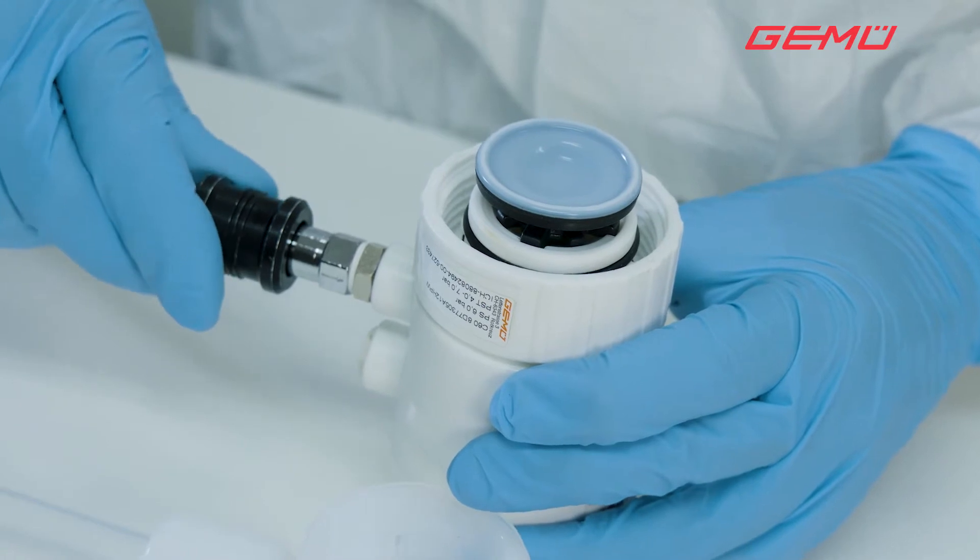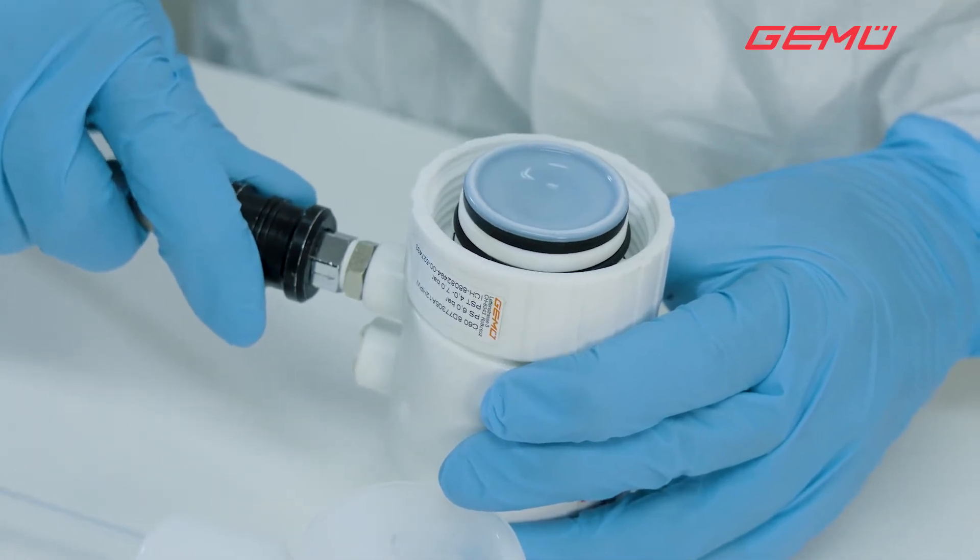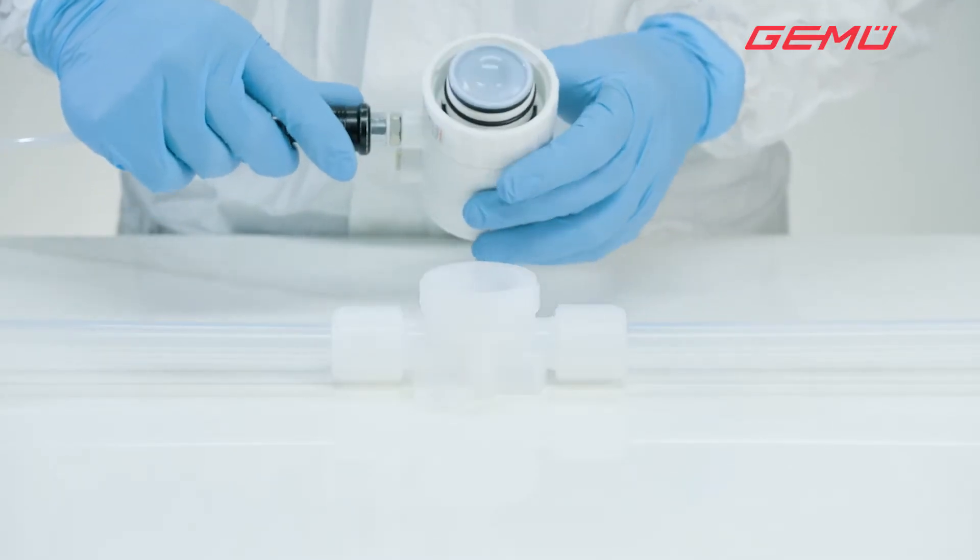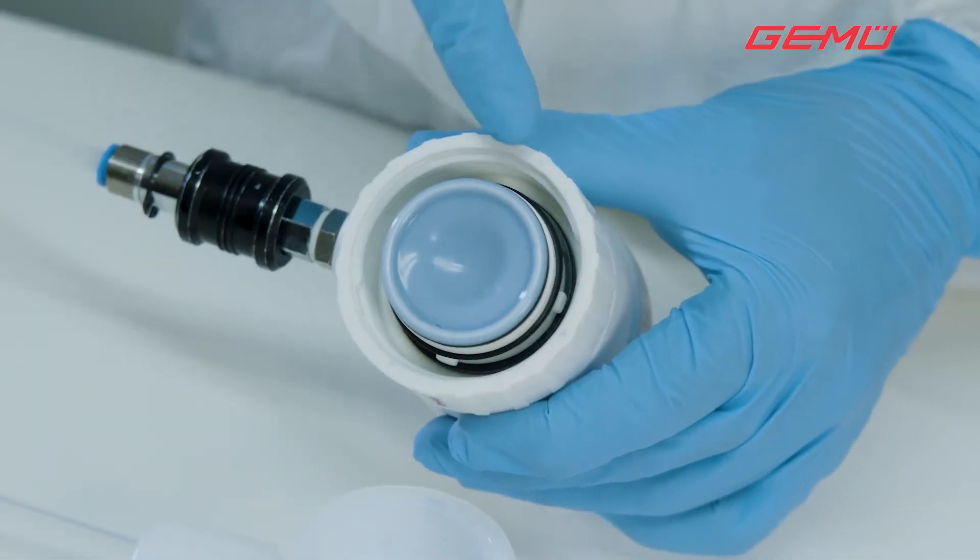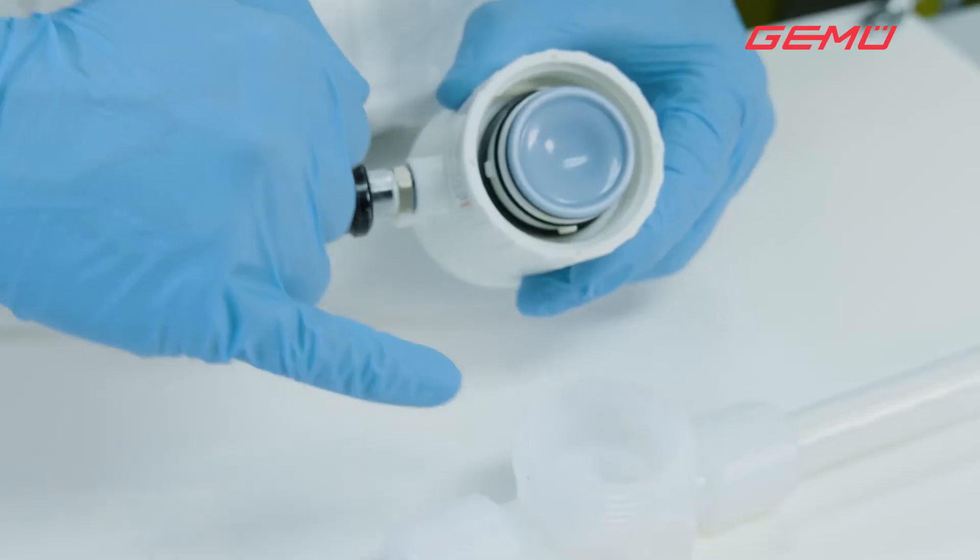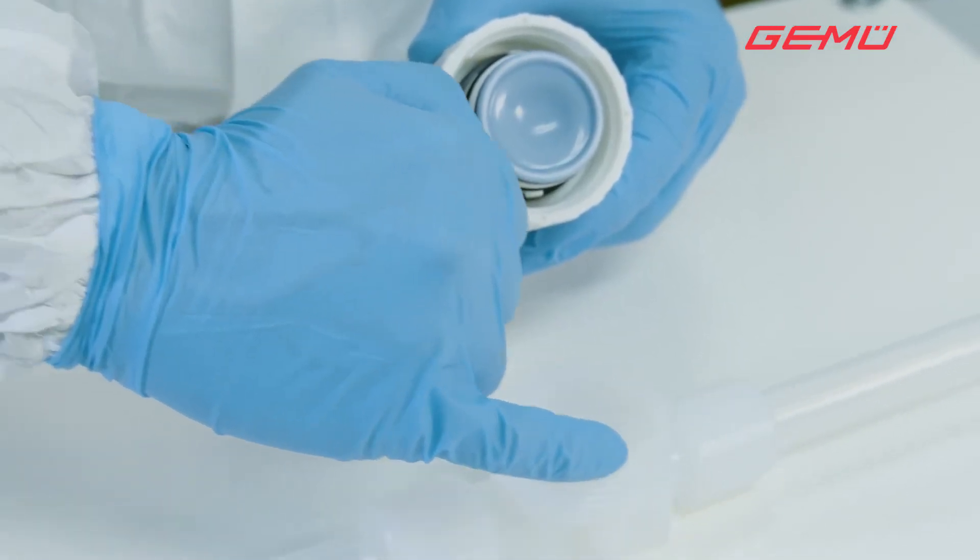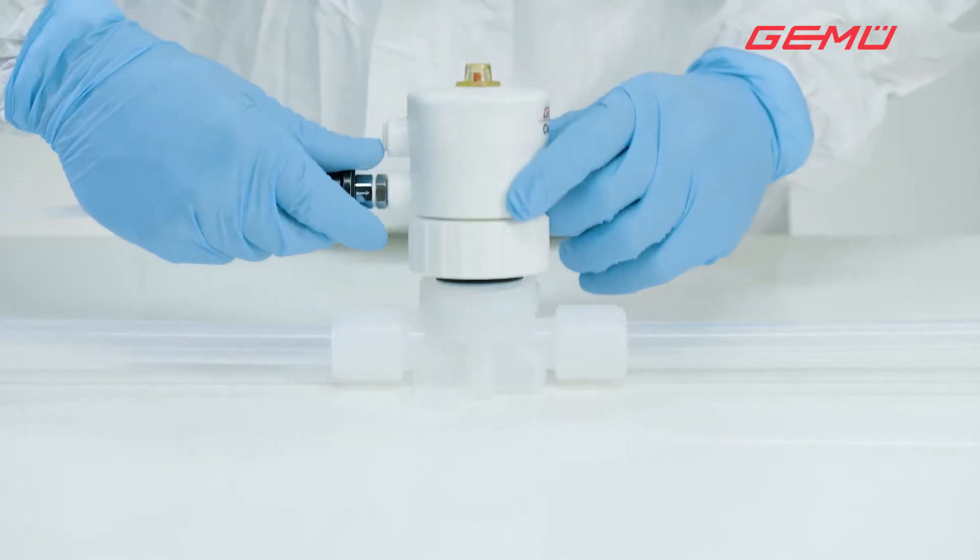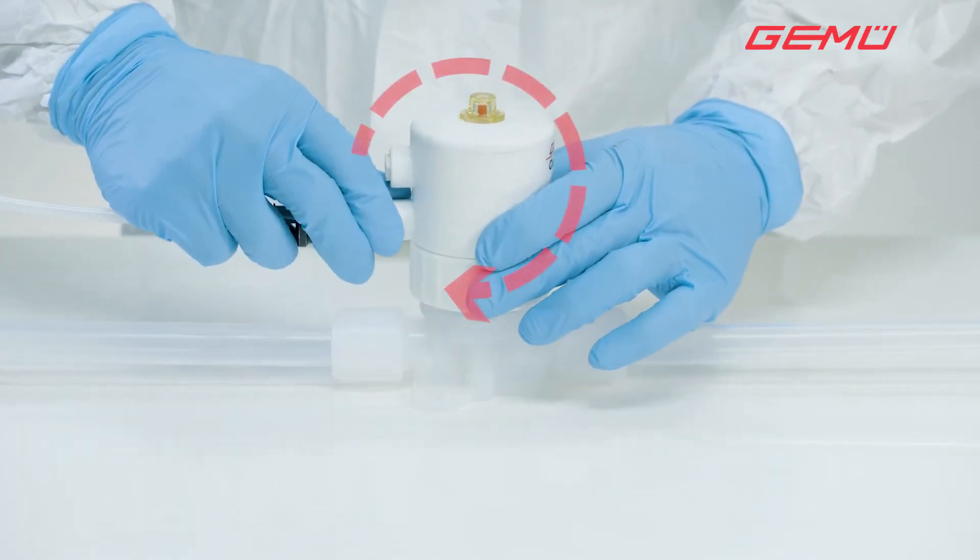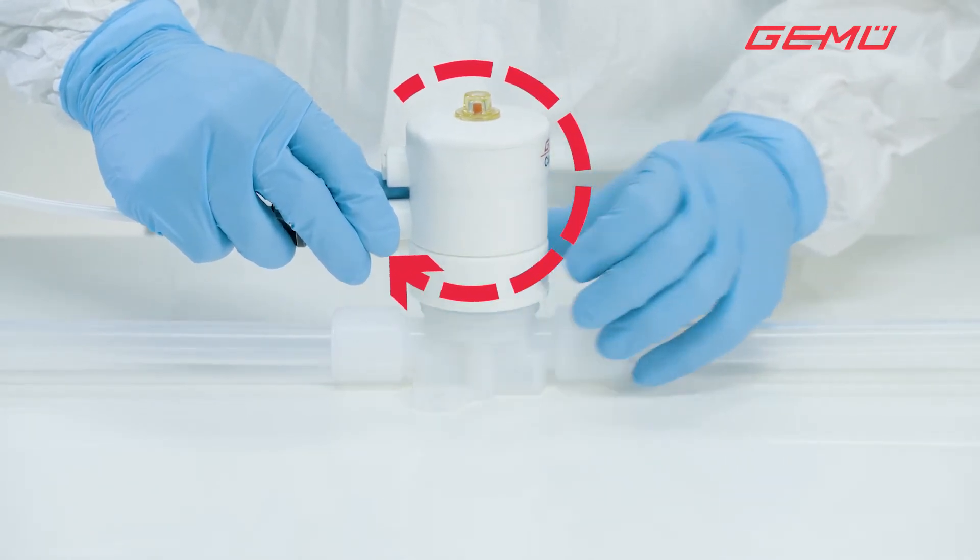Move the actuator to the open position. The fixing lugs in the actuator and the fixing grooves in the valve body indicate the correct installation position. Position the actuator on the body and tighten the central nut clockwise until it is hand tight.